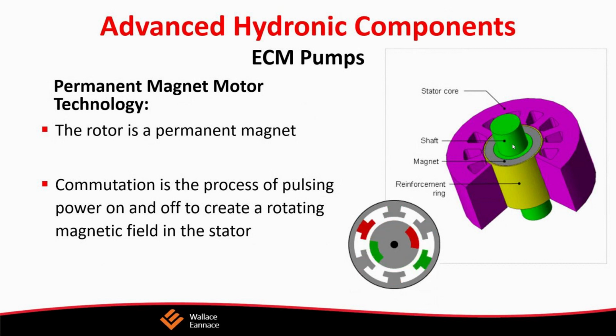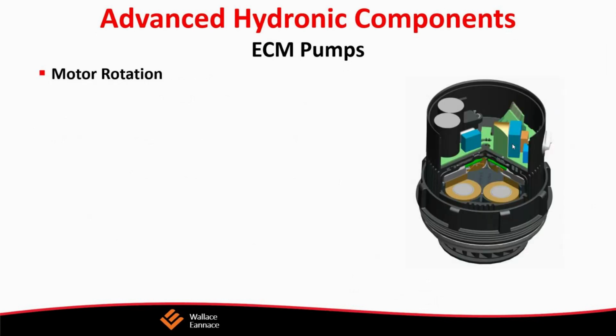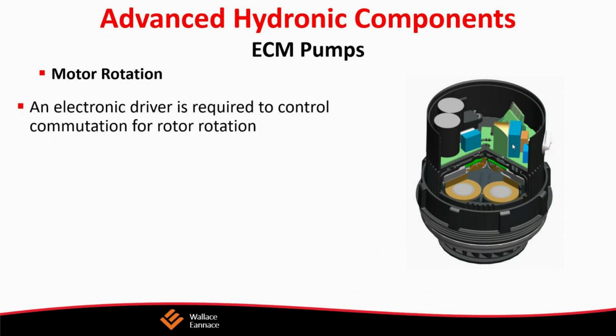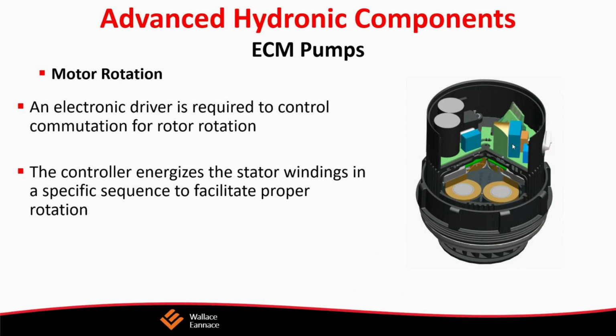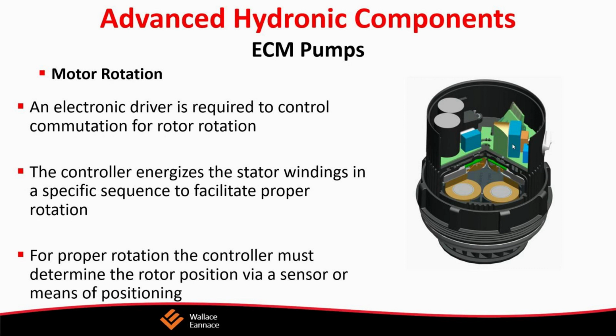AC circulators don't have permanent magnets. Electronic commutating motors have permanent magnets on the rotor. This inherently saves electrical power because you're not required to input some power to induce the magnetic field on the rotor side for proper rotation. AC circulators will always exhibit motor slip. There's always a lag, always a space, and that is part of the function of inducing the magnetic field on the rotor. ECM circulators will not have this, as the magnets are present on the rotor, and this gives ECM circulators the advantage of responsiveness to system changes.